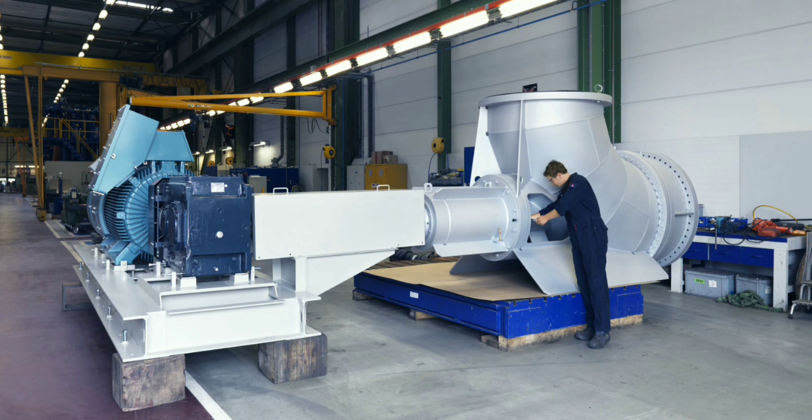Let us see the advantages of an Axial Flow Pump. It has a high flow rate — axial flow pumps are capable of handling very high flow rates, making them useful for flood control by moving large volumes of water. It is well suited for applications with low head requirements and is generally more compact compared to a centrifugal pump.